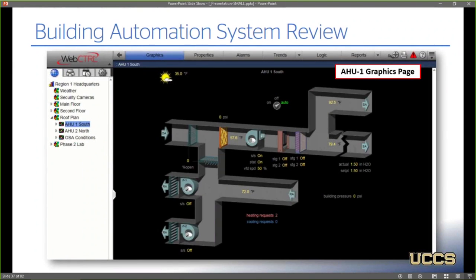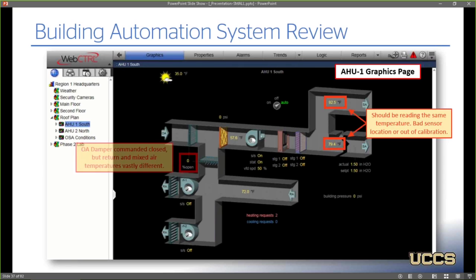So here's a screen grab of one of the office air handling units, and I hope it's come through your screen okay. Just to identify some of the anomalies I found. The supply air, after it leaves the coils, there's a T in the ductwork where it splits and goes to different areas of the building. Now, these two temperature sensors should be reading about the same thing, but they're reading almost 12 degrees apart. So it could be bad sensor location or it's out of calibration, but something is definitely not right there.